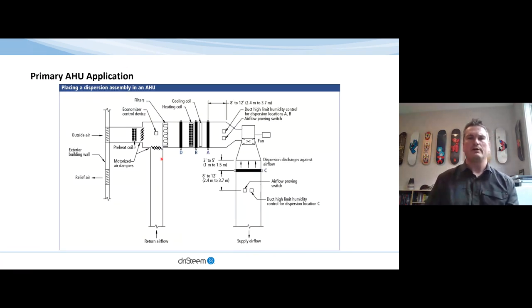If we look at it only as a primary air handling application, and we're just going to keep a generalized relative humidity control, there are different ways to approach this. If we have a pressurized or an isothermal system, we probably want to keep our steam dispersion after the heating and cooling coils, because if we apply the moisture after the heating coil but before the cooling coil operating at a very cold temperature, we're probably going to be drying out our expensive moisture that we just produced. However, another thing we need to consider again is that absorption distance. If we're introducing 55-degree air upon a steam dispersion, it may take longer to absorb that moisture.